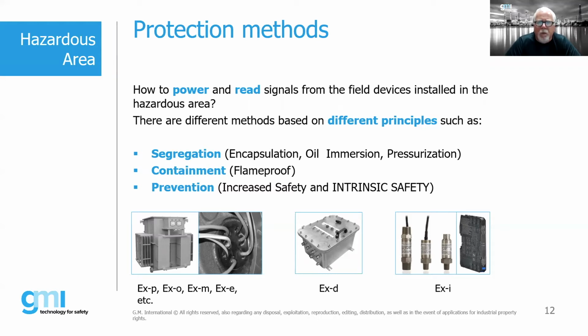But basically what we're trying to do with the ignition triangle, we're either segregating it, and segregation is taking things like encapsulating it, like taking something which is called EXM, and we're putting a resin. We could oil immerse a potential arcing component. We also could pressurize it, so we're using a pressurized enclosure. So we're removing one of the legs of that triangle. In this case, we're basically removing, in effect, that arc or spark away from the flammable atmosphere.